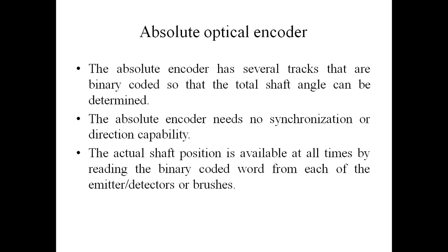It therefore has one output for each output code bit, and as the resolution increases, the number of outputs increases. Rotation detection is accomplished by directly reading the output code. When the encoder is incorporated into a machine, the zero position of the input rotation shaft is fixed, and the rotation angle is always output as a digital value with the zero position as the coordinate origin.